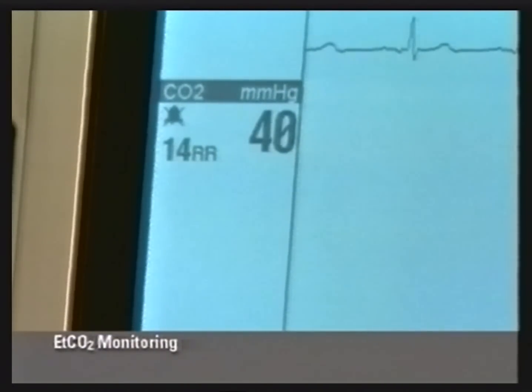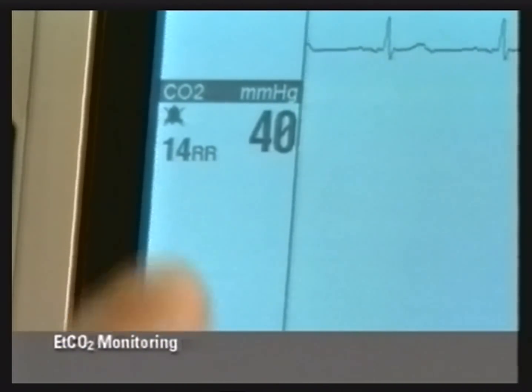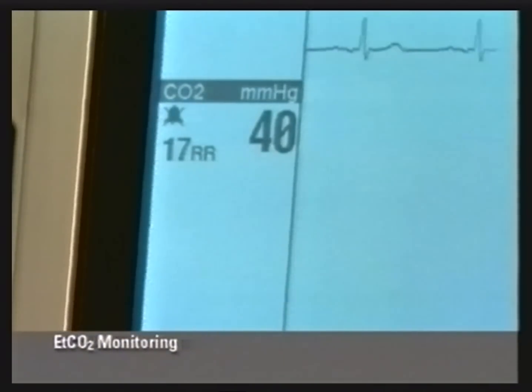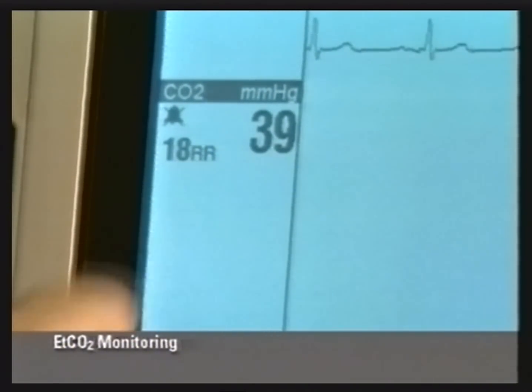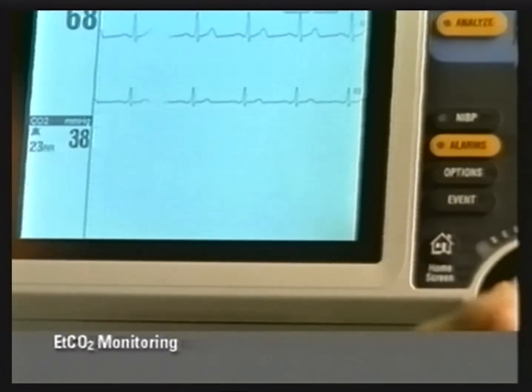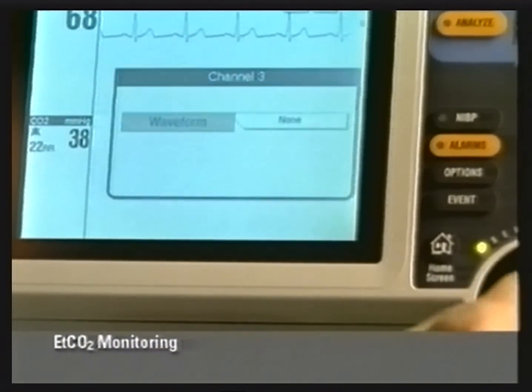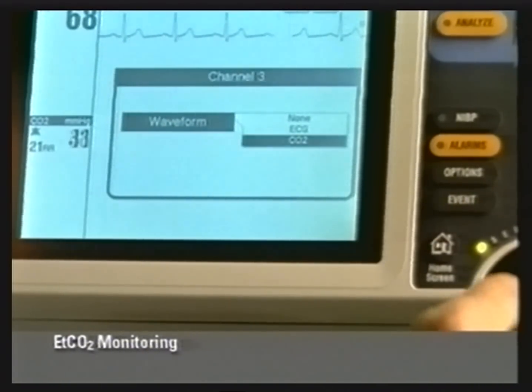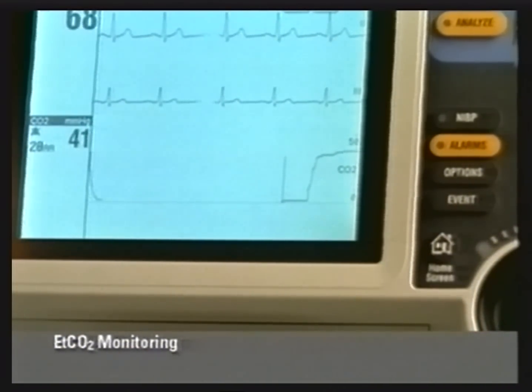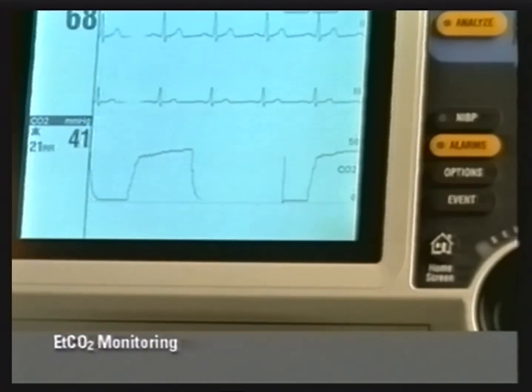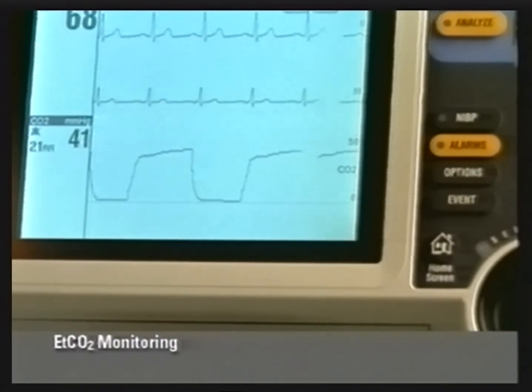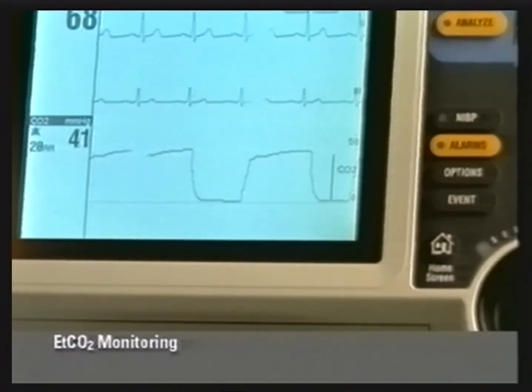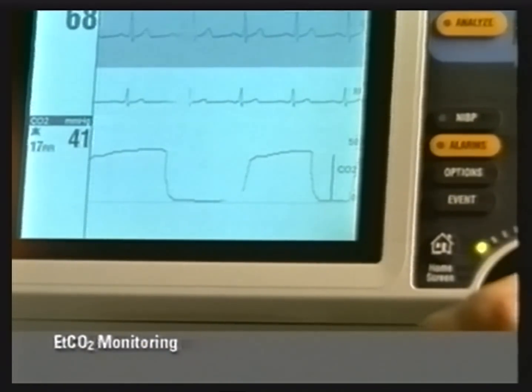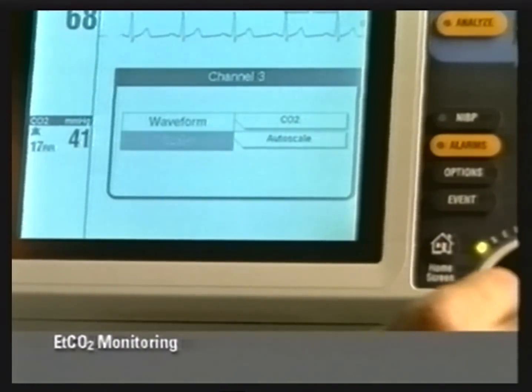The CO2 area on the screen displays the end-tidal CO2 measurement in millimeters of mercury, percent, or kilopascals. These units of measure must be pre-configured in the monitor. The CO2 area also displays respiratory rate in breaths per minute. To display the CO2 waveform, select channel 2 or 3. Select waveform in the channel overlay and select CO2. The continuous CO2 waveform is displayed along with a scale on the right side of the screen. For more detail about the phases of the CO2 waveform, consult the operating instructions. To change the CO2 scale, select channel 3, select scale, and then select the desired scale range.